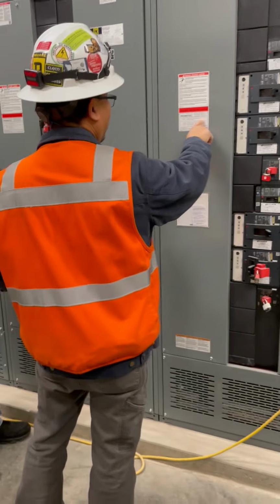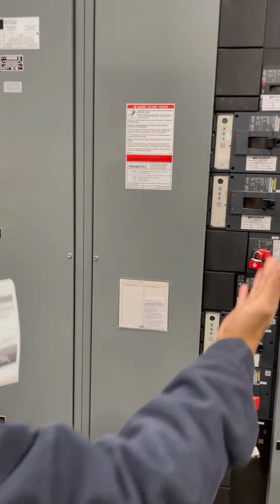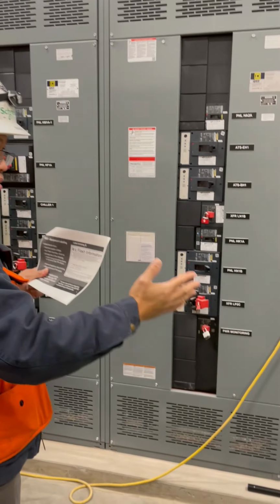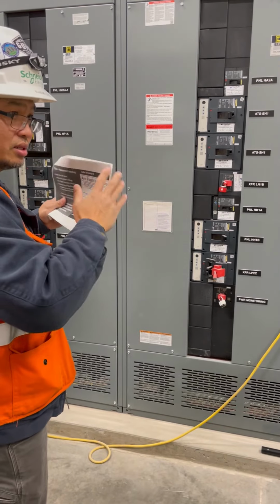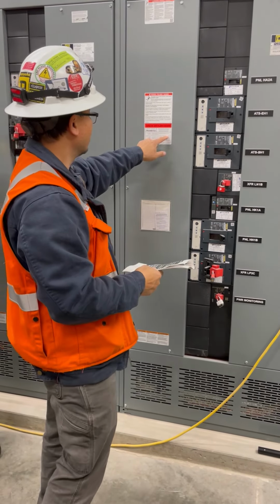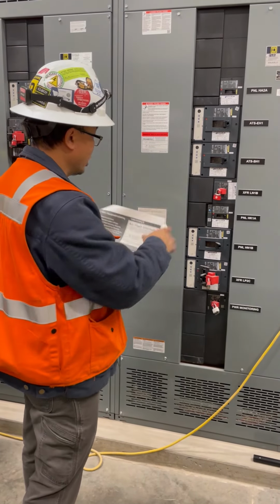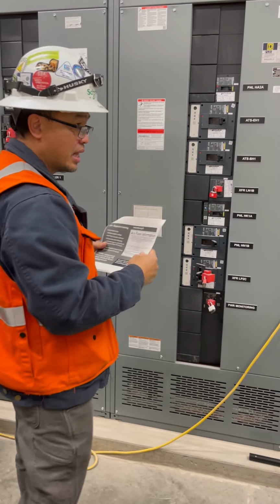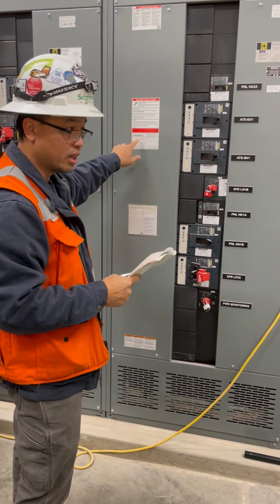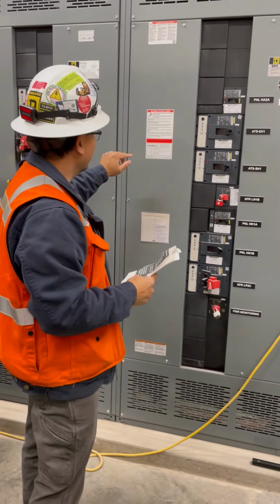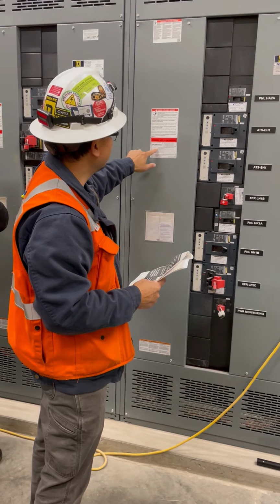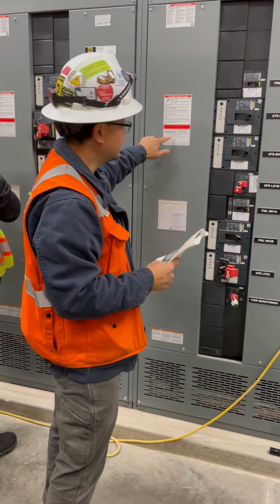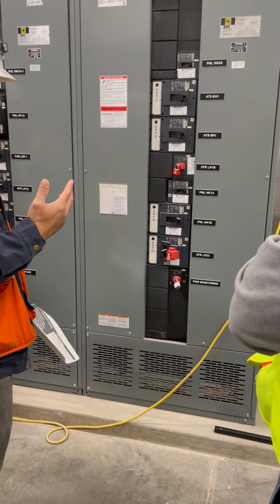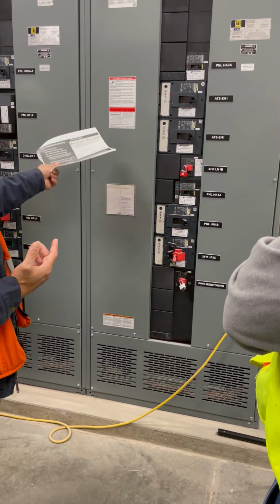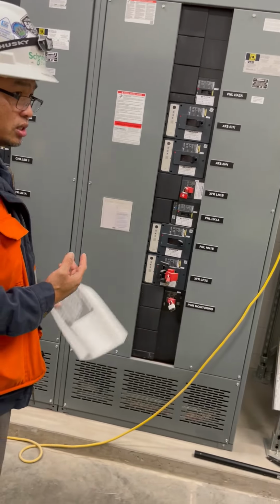So this is the energy at 1 foot 6 inches, 18 inches. That's the standard for most people. Some people are longer, some shorter, so this is the average, and the standard calculations are based on 18 inches. If you're 18 inches away from an exposed conductor, exposed live parts, that is the incident energy, 77 calories per centimeter squared. They also give you the arc flash boundary, that's 11 feet 7 inches. At 11 feet 7 inches you can be exposed to a second degree burn, which is 1.2 calories per centimeter squared.